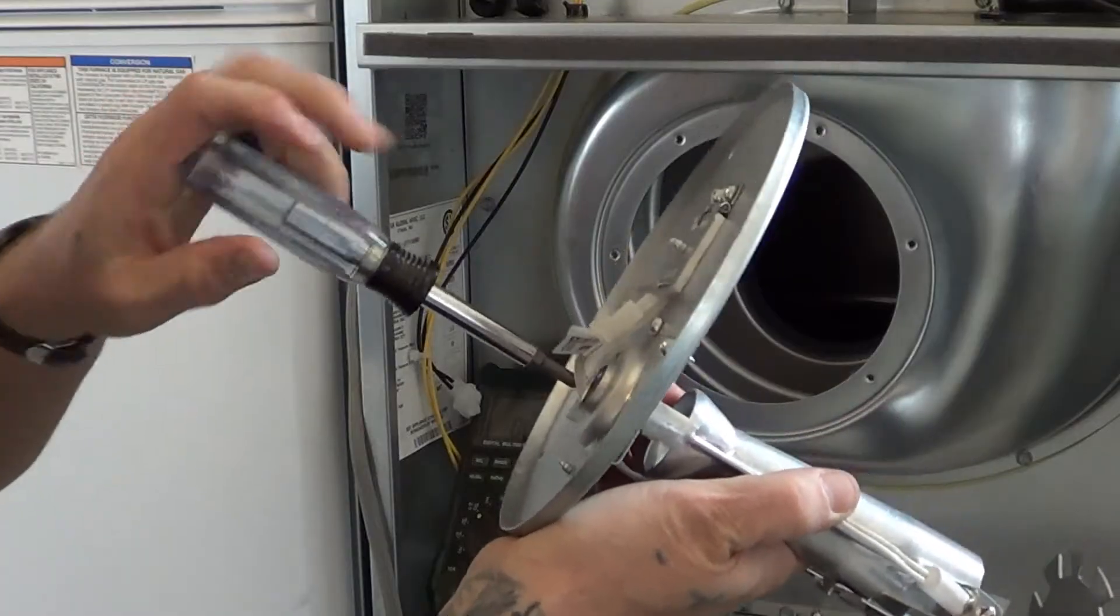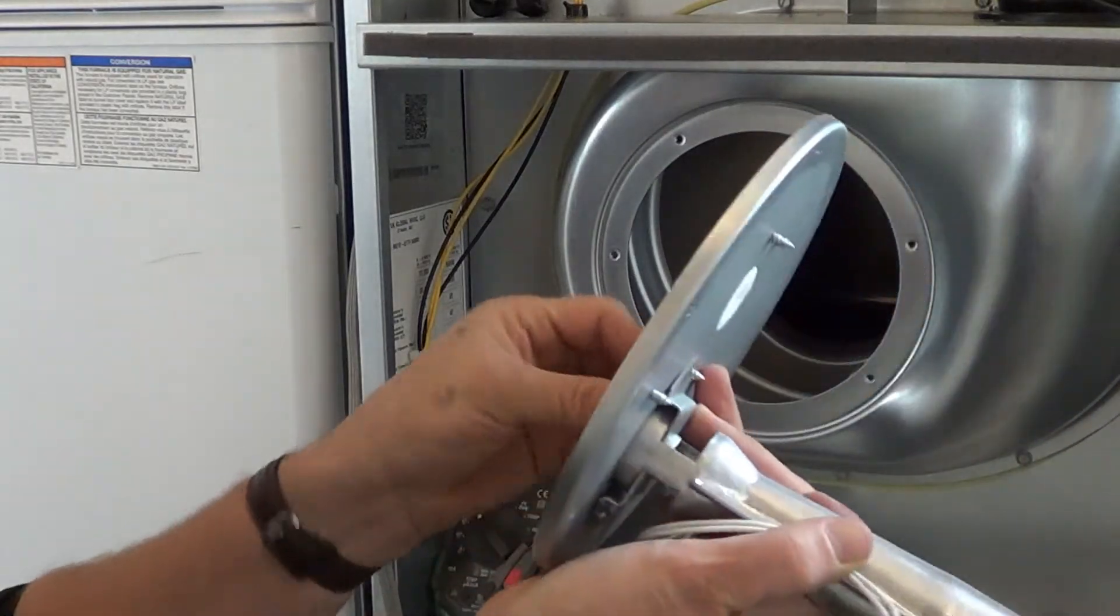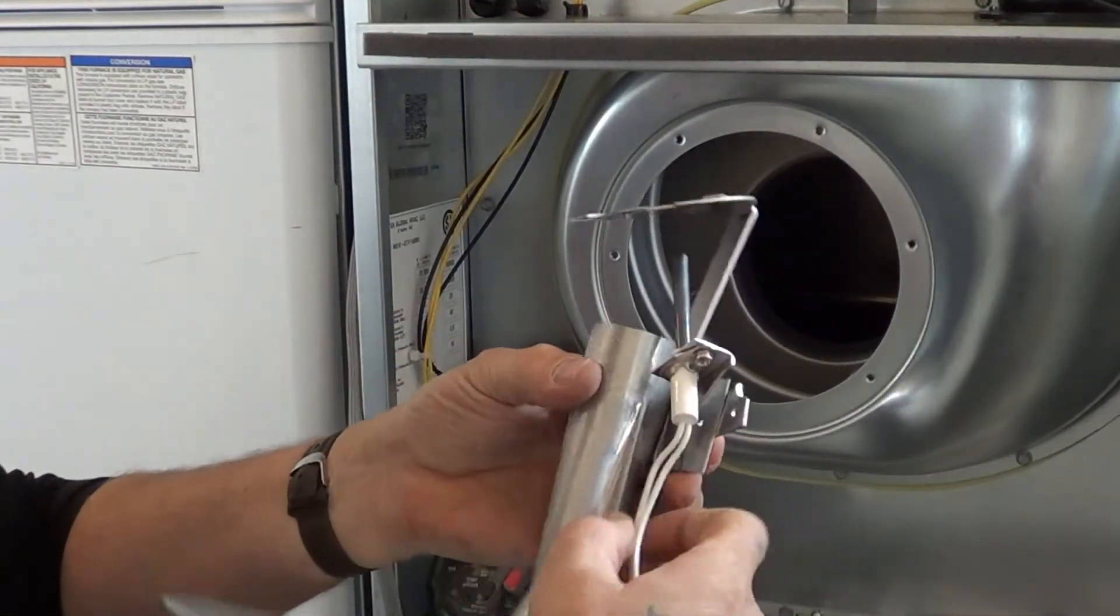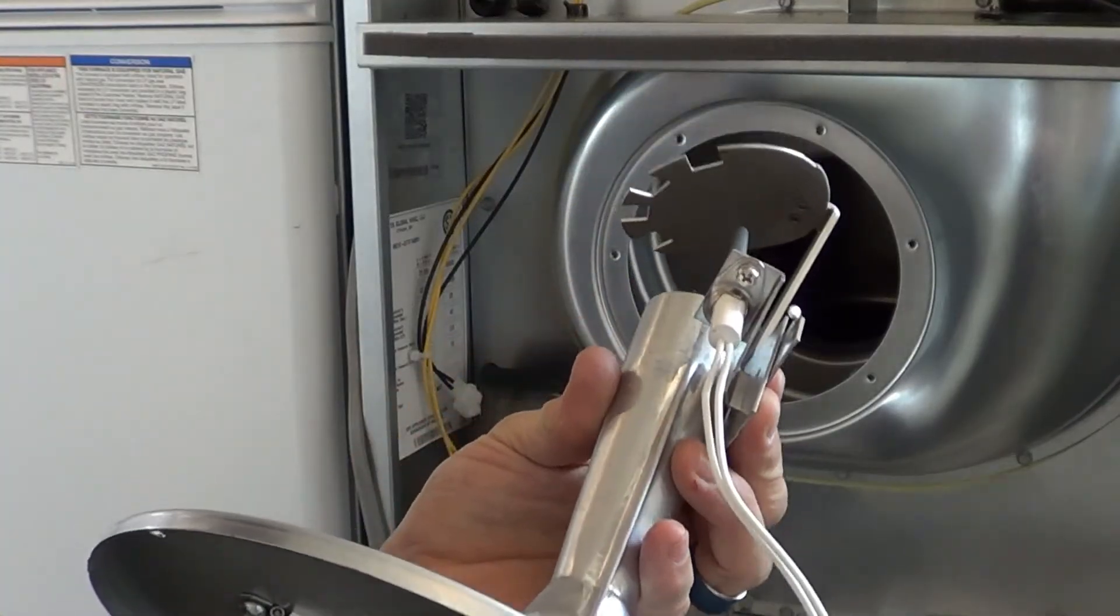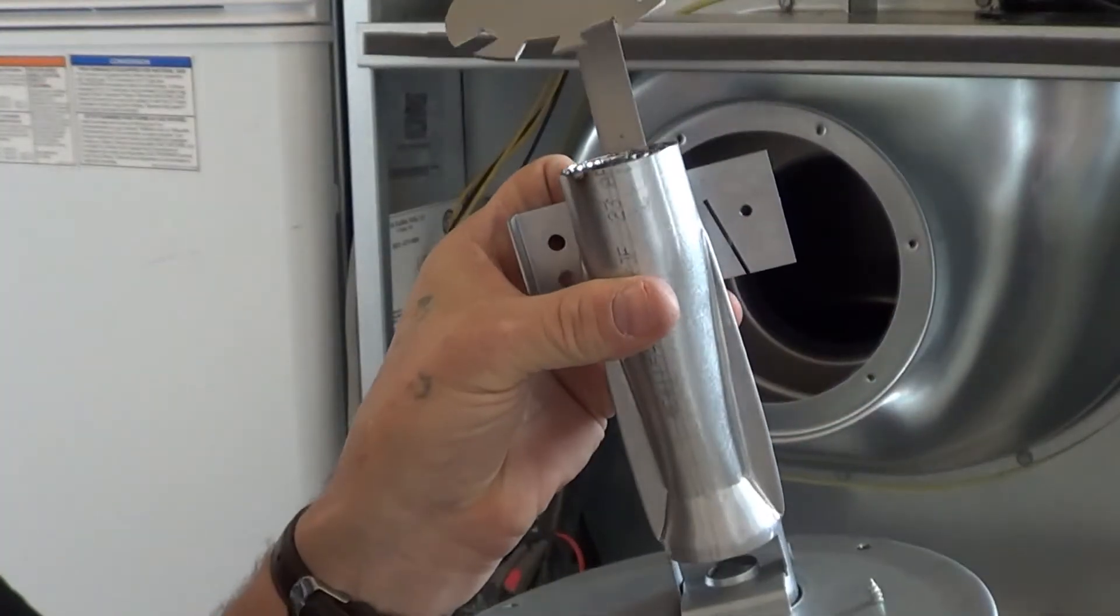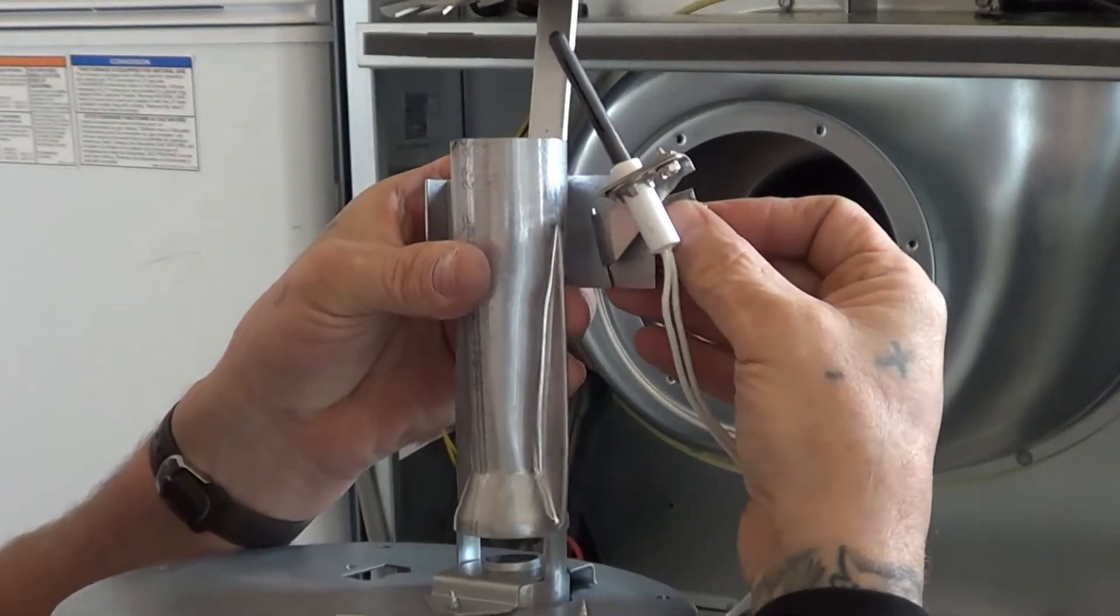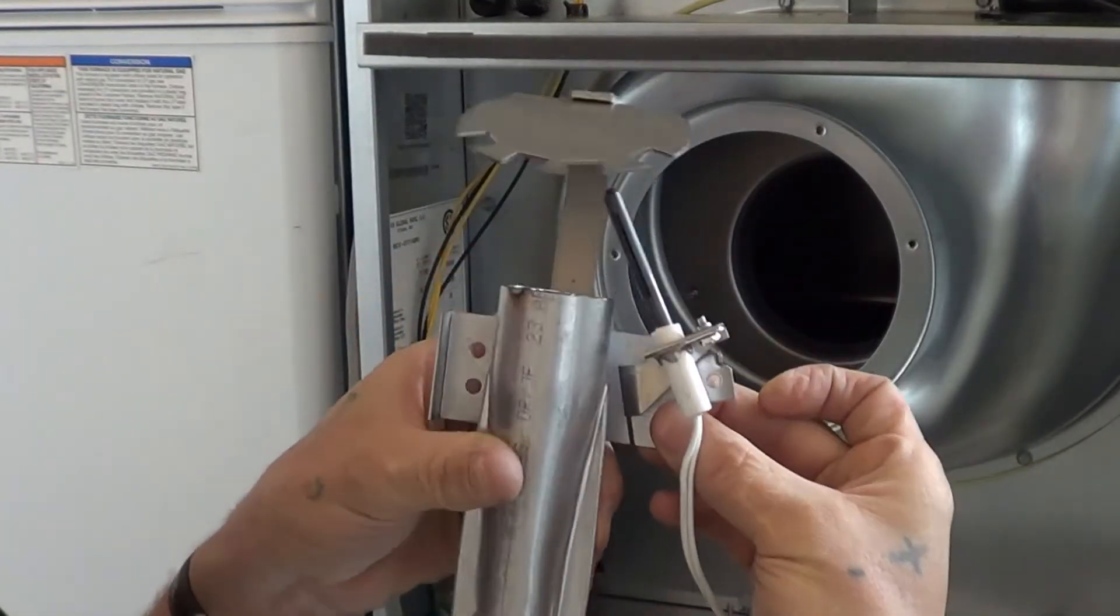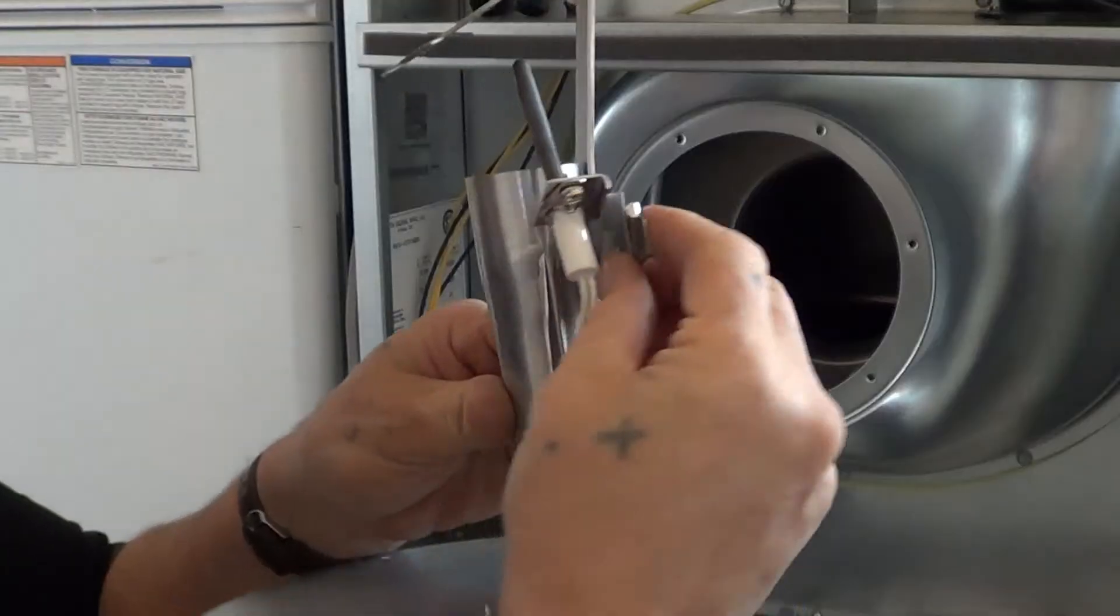Taking that little plate off—the wires will come through this way. I really suggest, because it's very important, that on this furnace you want the correct igniter for that furnace. This one has a little bracket that slides precisely at that angle so when I put this in, I need that igniter to fit that much into this flame. When I get the igniter, I need this igniter—I don't want to get a universal, I want to get the igniter for this one.